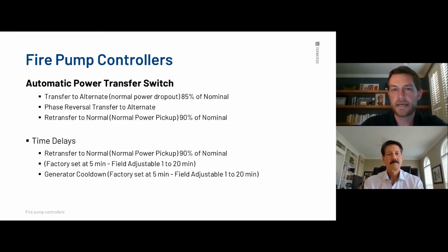It will transfer over to alternate, and then it doesn't come back. It'll switch back automatically after it's gotten to 90% healthy voltage. But where it says down there below, where it says time delays, it's going to have to see healthy power for 5 minutes. It is field adjustable from 1 to 20 minutes. But the control panel needs to see a healthy voltage on the normal side before it's going to switch back over from the alternate side. And that doesn't happen until it gets to 90%. So 85% it switches over, 90% is when it'll come back. You can switch it, it is field adjustable. But from the factory, we like to have a 5 minute process before it sees healthy voltage.